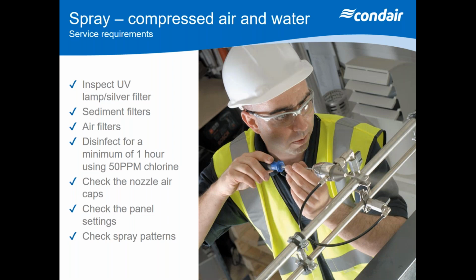Also, we need to make sure the panel regulation is checked on a regular basis each year, because you're going to find the regulators will change in terms of the seat of the regulation, and you might find that you have to go in and adjust that every now and again. And there's also a valve kit or a regulator kit that needs to be replaced every so often as well. If you've got particular tight areas, you can also adjust the individual nozzles. As you can see with our engineer Steve in the photograph there, he's tweaking that nozzle to give a finer spray just on that one nozzle. Ideally, if the system's set up correctly, you should have uniform spray across all the nozzles.